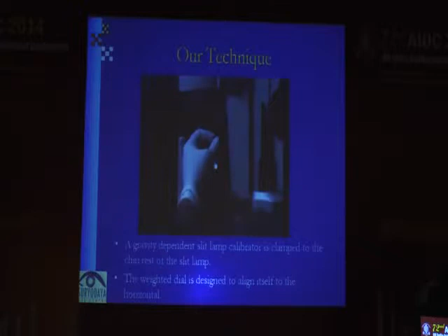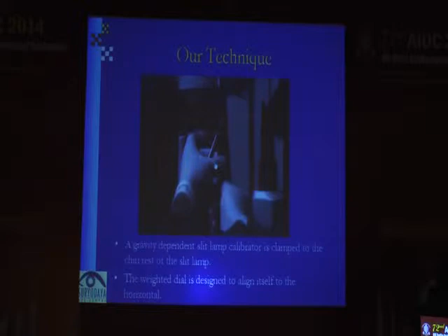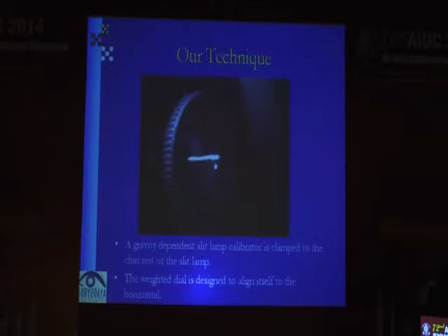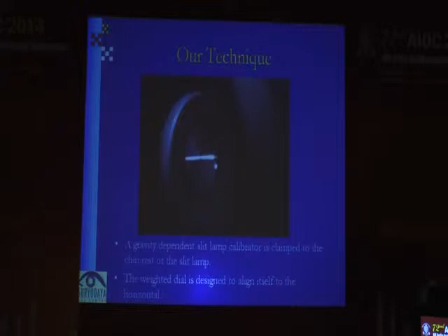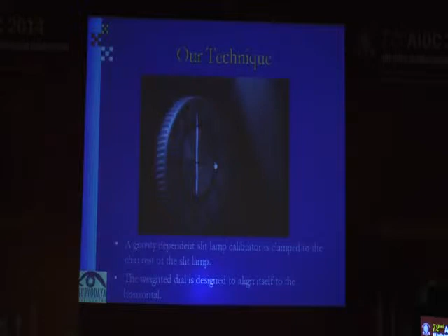So the next issue is, when I'm putting the slit lamp axis at, say, 40 degrees, how do I know that it is exactly 40 degrees? For that we have devised a very simple instrument which has a dial and a pendulum device which rights the dial. So whichever angle you place it, the 0-180 will always come to the gravity-defined 0-180. And you can turn the slit beam to graduate the exact axis of the beam.